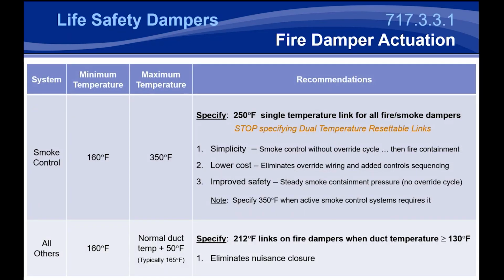When you're talking about fire damper actuation, or kind of what I was talking about with shutting those air handlers down, there are typically two buckets for fire damper actuation. Most of the time, fire dampers use a fusible link to shut down. It's just a bimetallic strip that separates and allows a damper to close either under spring power, under actuator power, or under gravity, depending on the damper design. Now, these dampers can be used in smoke control systems. Typically, dampers that are used in smoke control systems will be dynamically rated. A lot of times you'll be using a fire smoke damper in those applications that'll be actuated, and your fire smoke dampers actually have not a fusible link, but a thermostat that cuts power to the actuator and closes the damper under that application.